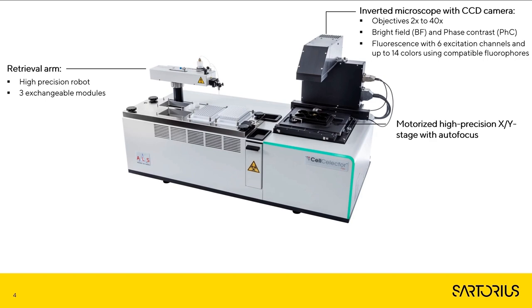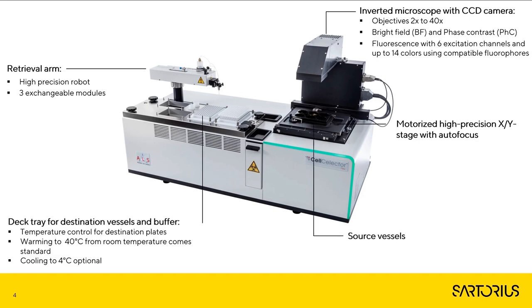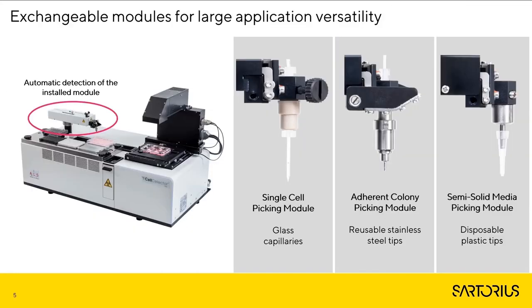CellCelector Flex is an extremely versatile system that can be configured to any picking needs. When configuring the system, it is possible to choose objectives between 2x to 40x magnification to allow identification from a large 3D structure to a single cell. Selection of up to 6 different excitation channels enables support for more complex phenotyping and multiplexing applications. Furthermore, an exchangeable robotic arm allows quickly switching between picking modules to extend application support. Once cells have been moved to the destination plate, this plate can be heated or cooled based on needs — for example, for omics experiments, sample cooling during extraction is crucial to ensure better stability of DNA, RNA, and protein structures.